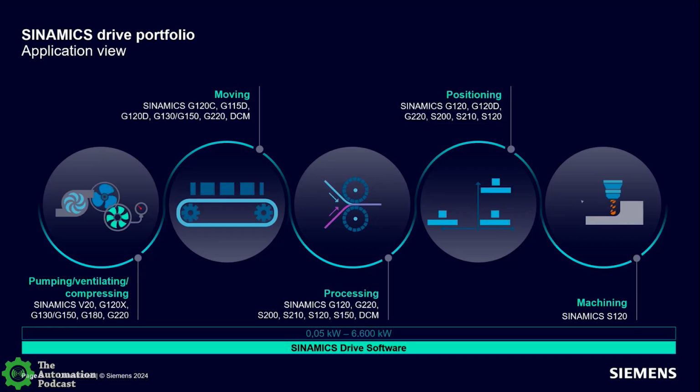There's also a lot of safety now, where they need the drive to have the safety capabilities just because the application demands it. And then we have inertial braking, dynamic brakes, and shared buses. There's so much in this field that you can do with drives. When we start talking about common buses or braking, a lot of times it's braking for safety. If somebody's hand gets stuck, we need to stop those pinches fast, or we need to stop the momentum fast. In other cases, we open up the pinches, of course. There are just so many cool and interesting applications in VFDs alone.